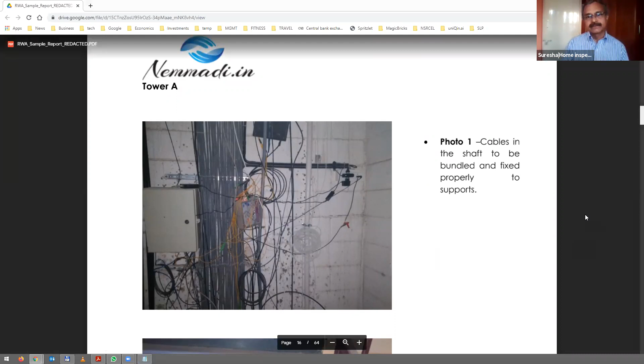This is the inside view of an electrical shaft. If you look at this, the electrical wires, data wires, telephone wires, and communication cables are all mixed up. This is a serious hazard, because there will be electrical interference and signal interference between the links, and also something can go wrong if a communication technician gets into the electrical shaft. This is a total no-no.